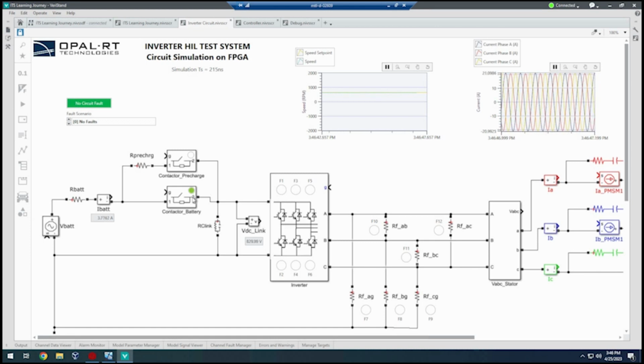From here I can see that my contactor, my battery contactor, has been closed already, and I've put some basic indicators of the status. Here you can see my battery current, or the current coming through the battery. We can see that our DC link is being regulated at 830 volts. And then we can see where the rest of the circuit pairs up to our machine, and where we can see our machine currents, which are currently sinusoidal.